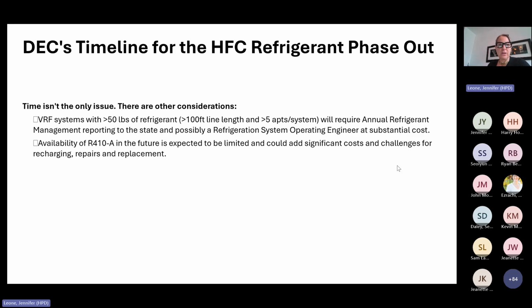A couple other considerations about refrigerants came up as we assessed this. One is that larger VRF systems—meaning over 100 feet of line length, typically more than 5 apartments per system—require annual refrigerant management reporting to the state, which could add substantial cost to a project.